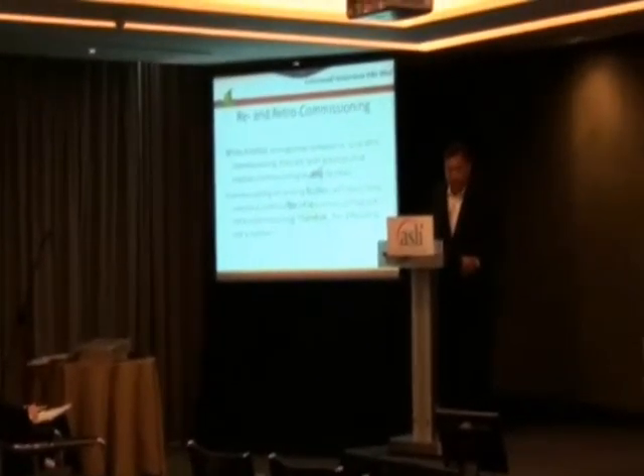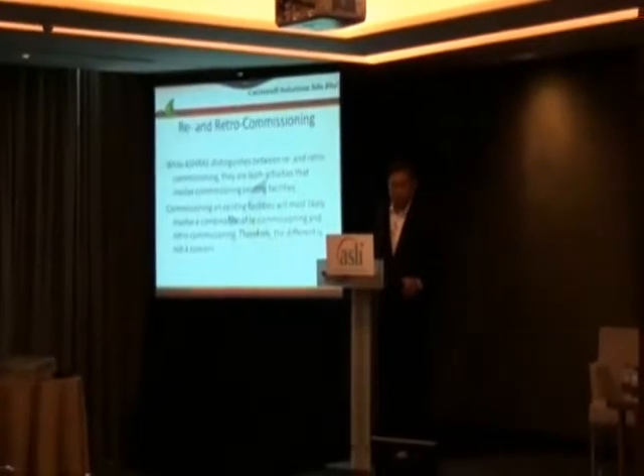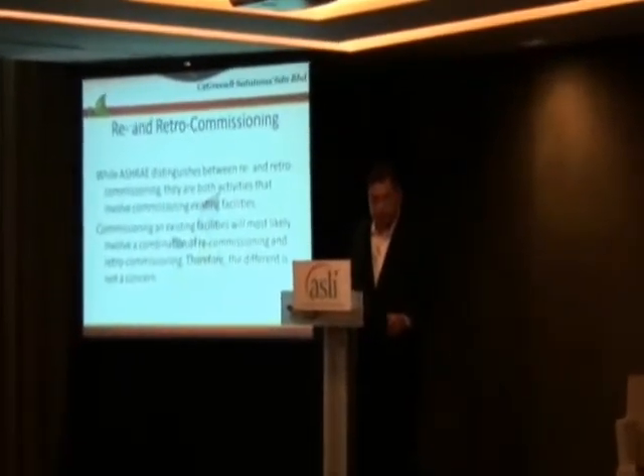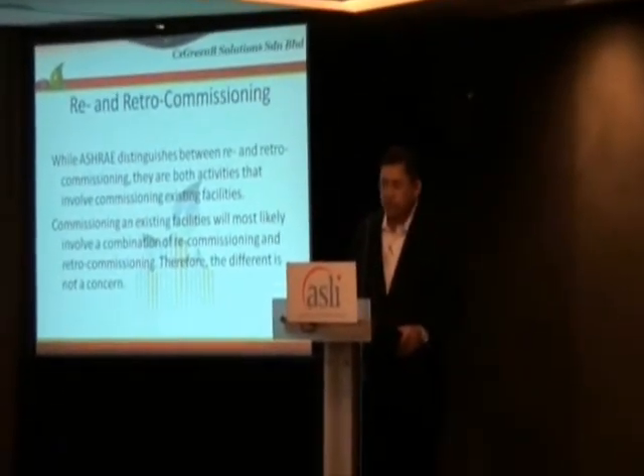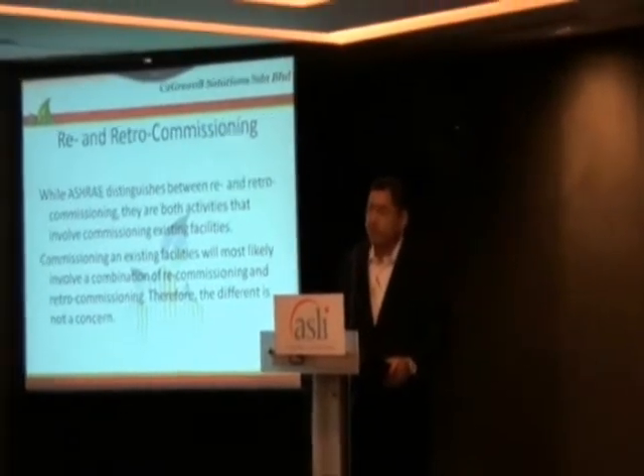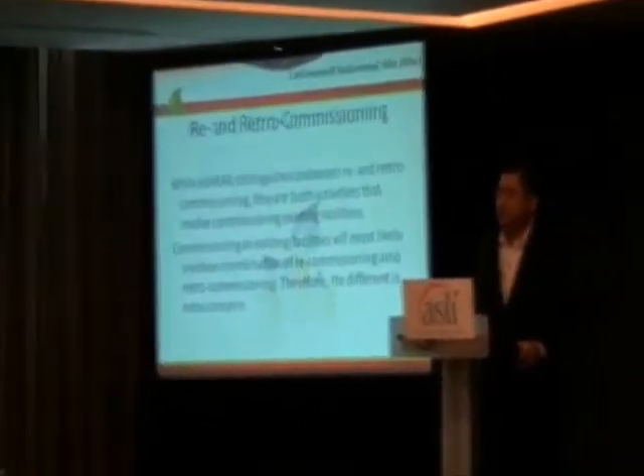So, how does ASHRAE distinguish recommissioning and retro-commissioning? Both activities involve commissioning of existing facilities. Commissioning existing facilities will most likely involve a combination of recommissioning and retro-commissioning. Therefore the difference is not really much of a concern, because there are systems that have been commissioned before but not fully, and you want to do it again.